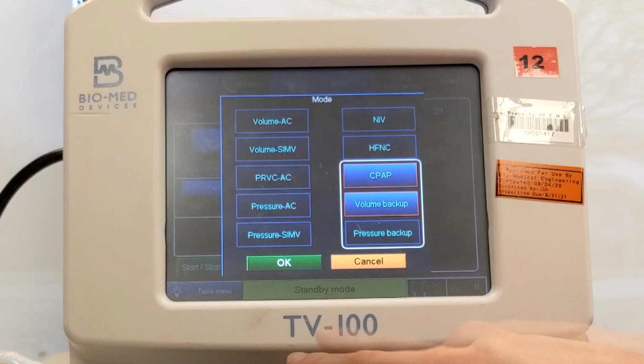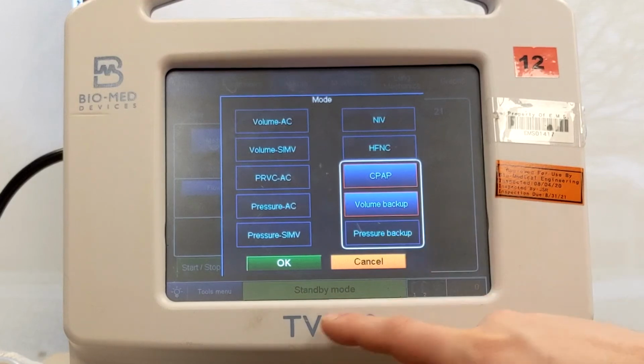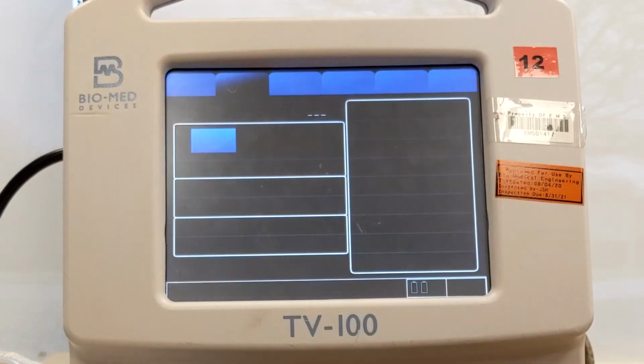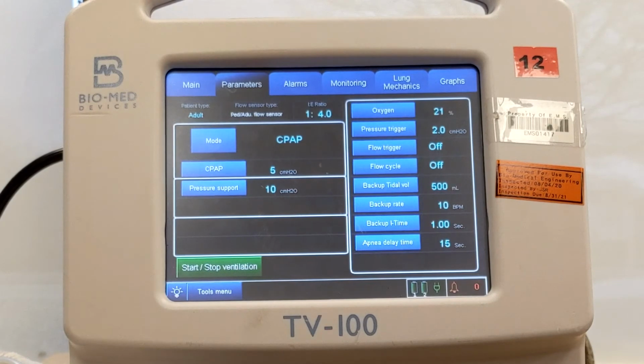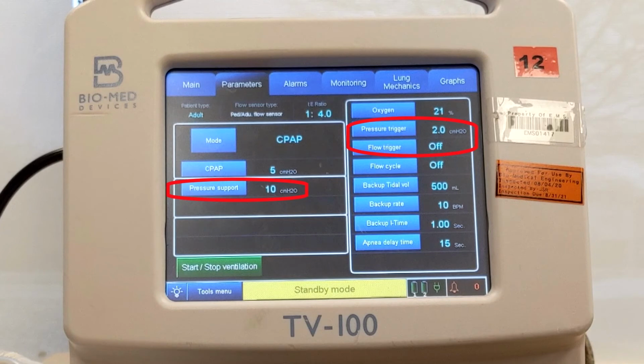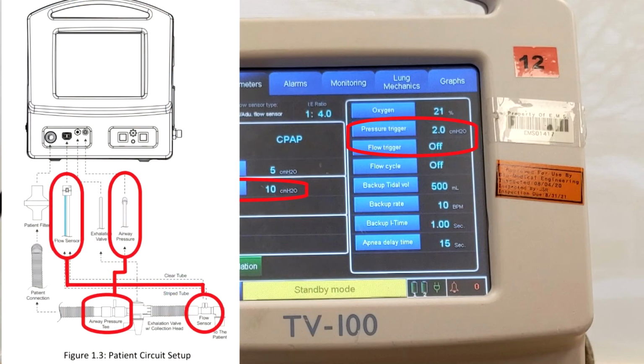In this mode, the TV-100 delivers a minimum continuous pressure during ventilations as well as manual or spontaneous breaths. If pressure support is enabled, pressure support breaths will be triggered by the patient's inspiratory effort via flow or pressure triggers. Pressure support breaths are triggered by the flow sensor, or if there is no flow sensor present, via the airway pressure line.